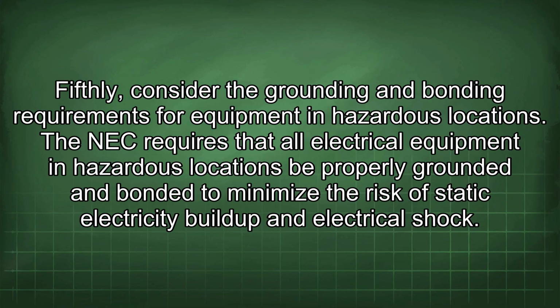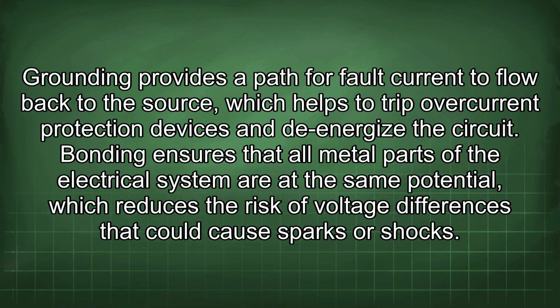Fifthly, consider the grounding and bonding requirements for equipment in hazardous locations. The NEC requires that all electrical equipment in hazardous locations be properly grounded and bonded to minimize the risk of static electricity buildup and electrical shock. Grounding provides a path for fault current to flow back to the source, which helps to trip overcurrent protection devices and to de-energize the circuit.